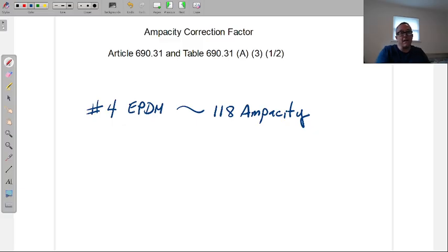Remember, the wire doesn't have this amperage. The wire is connected to a system, panel, whatever, that is going to deal with up to, and the wires are good, up to 118 amps. So any wire, any insulation type, find the ampacity. That is step 1.